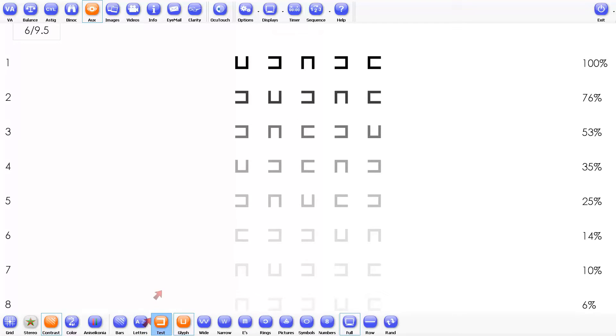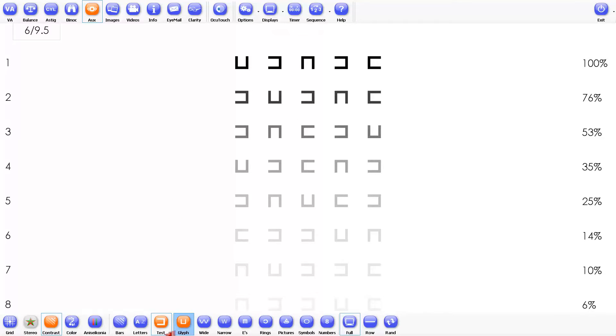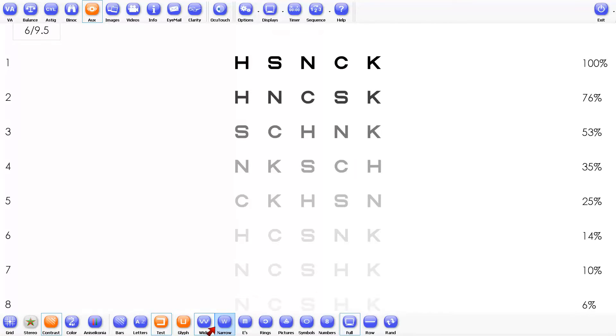Let's see how we do this test. Firstly, select Auxiliary from the top menu bar and Contrast from the lower menu bar. You can choose between the bar or the letter screener or the finer measuring test. In this case we choose the test and we choose the glyph optotype. You can choose any one of the others as is your personal preference.